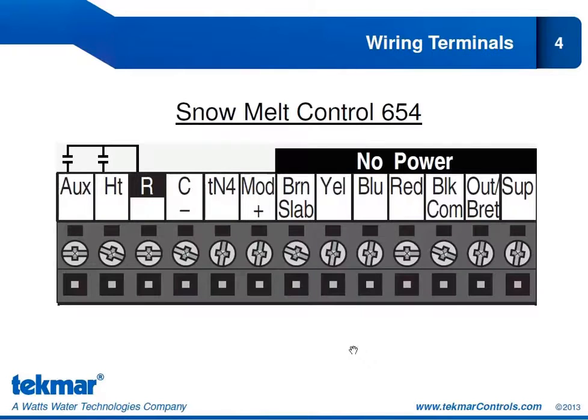Here's a close-up of the wiring terminals. On the right-hand side, you can see we have our terminal strips for the snowmelt sensor. So if we are installing a 090 or 094, we will connect the brown, yellow, blue, red, and black from the sensor to the 654. If we are installing a 095, the aerial mounted snow sensor, then of course we don't have that brown wire. We're going to be using the yellow, blue, red, and black. We also have a terminal for an outdoor sensor or a boiler return sensor. So this is a shared terminal between an outdoor sensor and a boiler return sensor. For the boiler supply or the mix supply sensor, depending on the application.